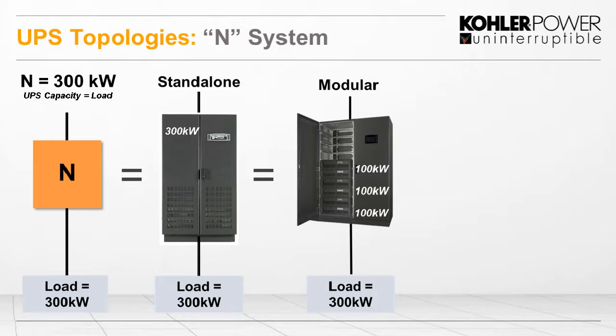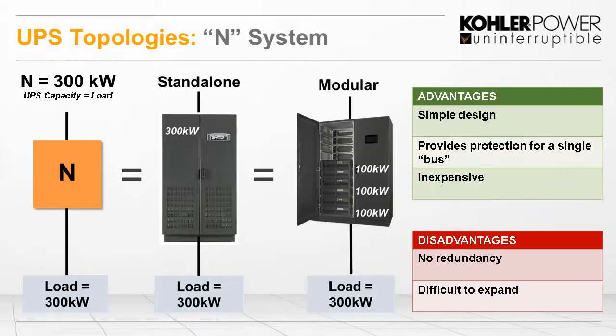So this can be done in a couple of ways. We can have one standalone monolithic box, which is capable of supplying 300 kilowatts, or we can make that up out of modules, or smaller modules, which makes it scalable. But we can look at the advantages and disadvantages. Now, of course, an N system is going to be the most simple of designs, and it does provide continuous protection to a single bus, and this is about as inexpensive as you're going to make it if you want power protection. However, there is no redundancy, and if you don't design it right from the beginning, it will be difficult to expand. And many people now want that redundancy.